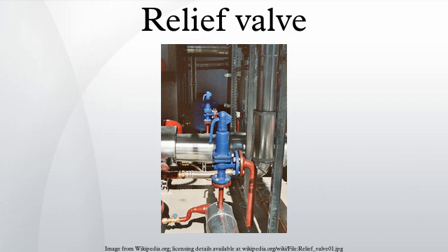Technical terms: in the petroleum refining, petrochemical and chemical manufacturing, natural gas processing and power generation industries, the term relief valve is associated with the terms pressure relief valve (PRV), pressure safety valve (PSV) and safety valve. The difference is that PSVs have a manual lever to activate the valve in case of emergency. Most PRVs are spring-operated. At lower pressures some use a diaphragm in place of a spring. The oldest PRV designs use a weight to seal the valve.